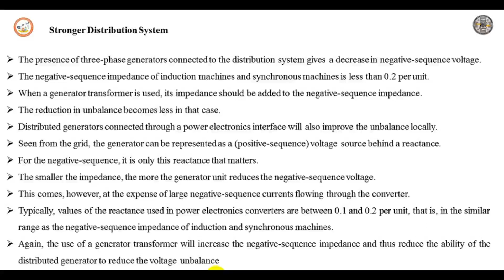The connection of a large single phase generator will result in the injection of positive and negative, and sometimes zero, sequence current of the same amount. The production of active power, P-gen, and zero reactive power gives current I equals P-gen divided by U, where U is the phase to neutral voltage at the point of connection. So it has been assumed here that the generator is connected phase to neutral.